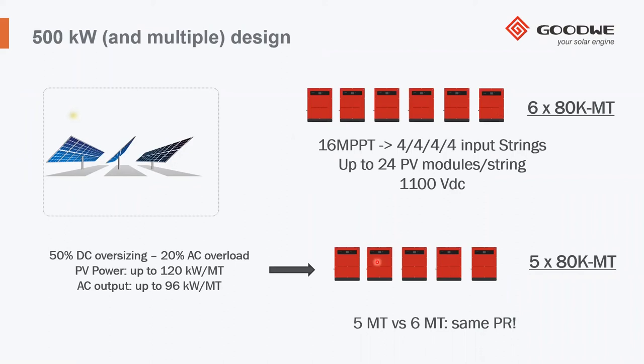But what we also put to your attention is, as I mentioned before, the capability of our system to work with 50% DC oversizing and 20% AC overload. If you take this into account, then it means that, as an example, an 80 kilowatt inverter can accept up to 120 kilowatt per MT, and you can have up to 96 kilowatt per MT machine. By taking this into account, then the design could be also by using only five 80K MT for a 500 kilowatt project. And according to our calculation, the performance ratio is exactly the same in the two cases. So we recommend this solution with six machines, but we also tell you, consider this possibility.